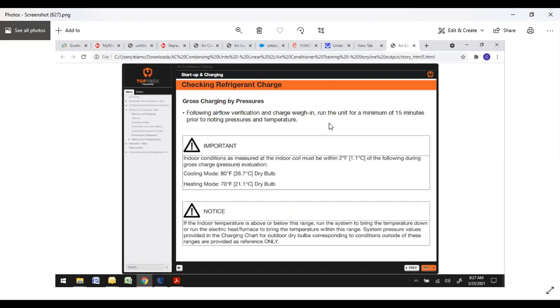So when you're checking your charge, this is huge. If you're putting one in in the wintertime, you can weigh in some additional charge if you need to, if you follow your chart. And that's basically what they call gross charged. It's a weigh in. So you assume minimum 15 feet. Take into consideration additional lines and additional fittings, and you'll be in the ballpark. For gross charging, you want to run the unit for a minimum of 15 minutes prior to noting pressures and temperature. If it looks off at first, just let it run, unless it looks way, way off, that's one thing. But if it looks a little bit off, let it run 15 minutes. It should be stabilizing by that point. At that point, you can start making your minor adjustments.